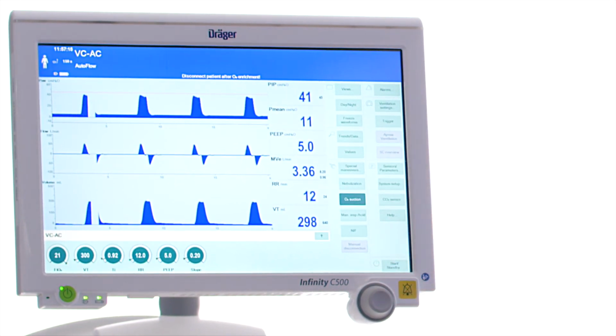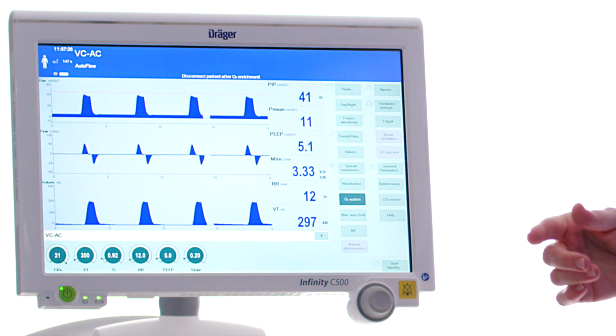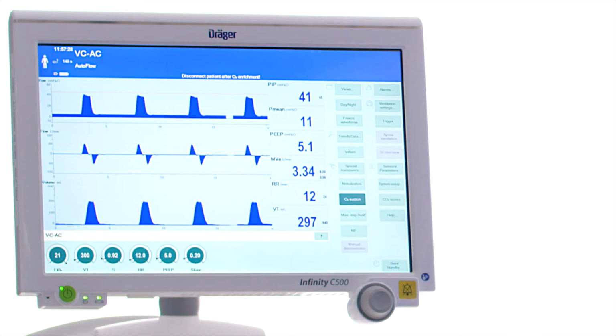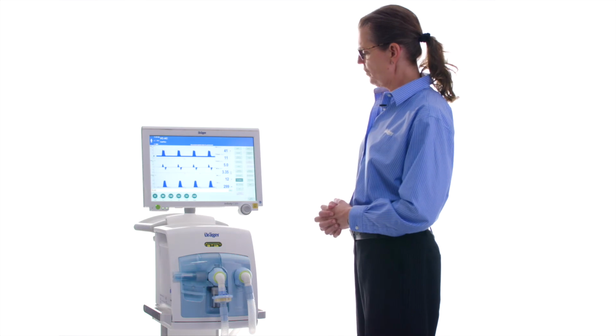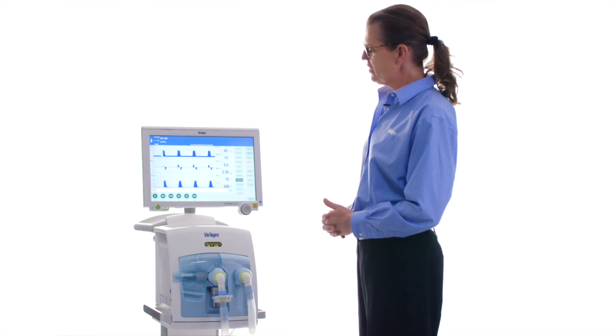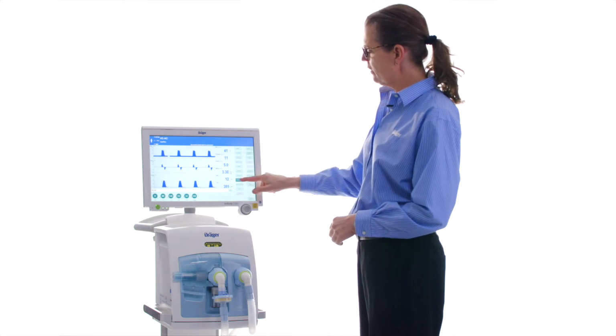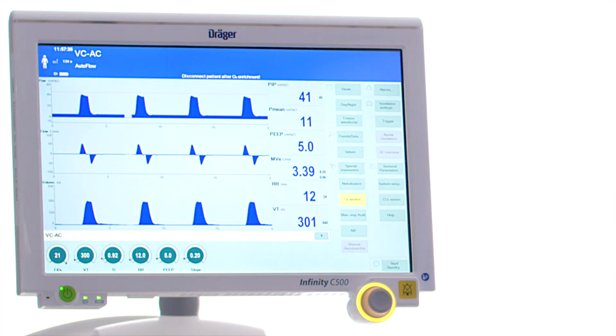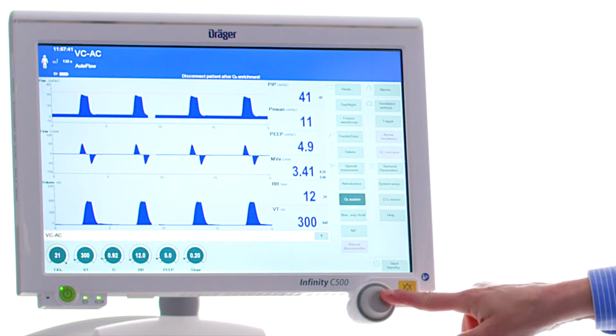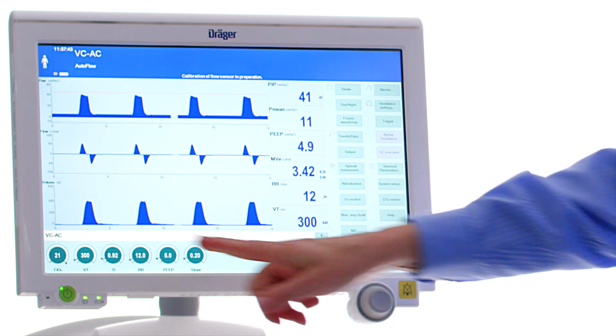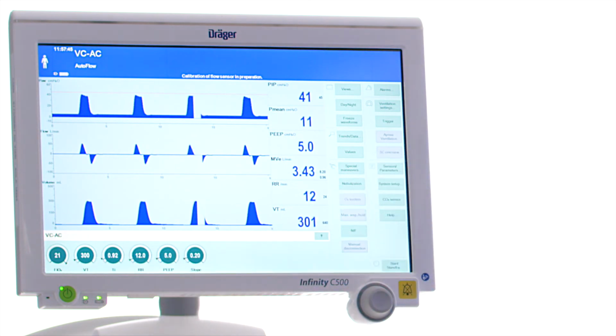O2 suction provides 100% FiO2 for 3 minutes. It also allows for disconnect without the ventilator alarming and spraying gas in the room, and will automatically go back to the set FiO2 at the end of those 3 minutes. To interrupt the O2 suction function and return to the set FiO2 immediately, simply touch the O2 suction button, which again will turn yellow. By pressing the rotary knob, it will reset the FiO2 to set value.